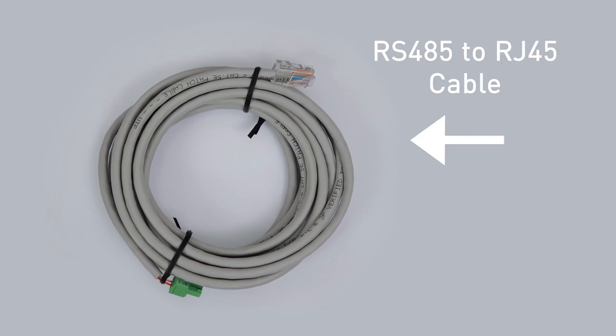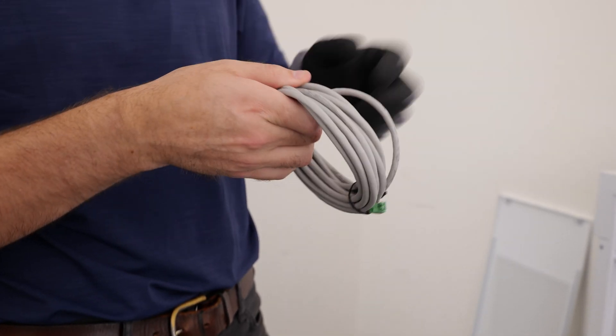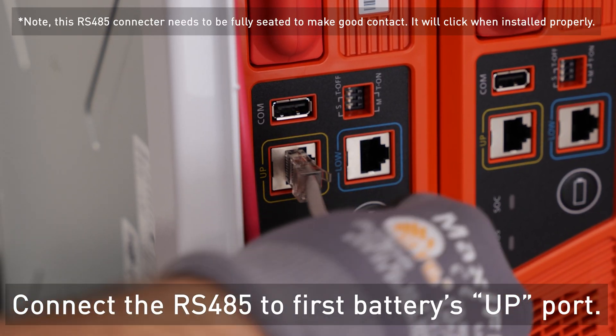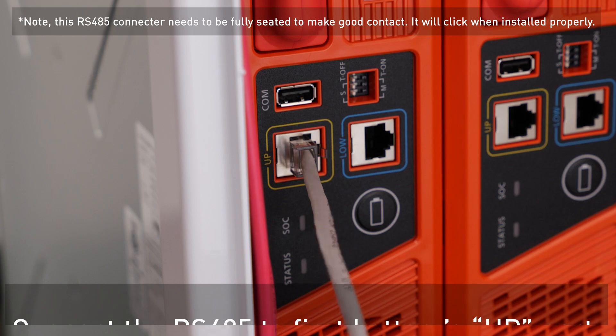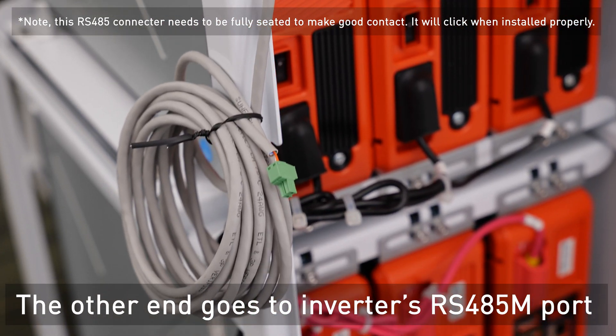Connect the supplied RS-485 to RJ-45 communication cables on the first batteries up port and route this cable back to the inverter where it is installed on the RS-485M port.